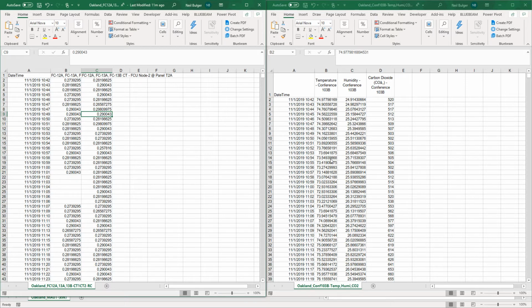If we need to answer questions against data, one versus the other, the only way to really do that is this 15-minute averaging. And if we just want to review the trends, sometimes stacking time over time and just putting this data right below this data and then looking at it all together, you would not be able to cross-reference them, but that is the smallest file size you will often find for a database, is just to have time repeat. Whenever a data point appeared at 1042, there's another row for 1042. That ends up being a very, very small file. So if our goal is to just visually review the data, that's a lightweight way to go.